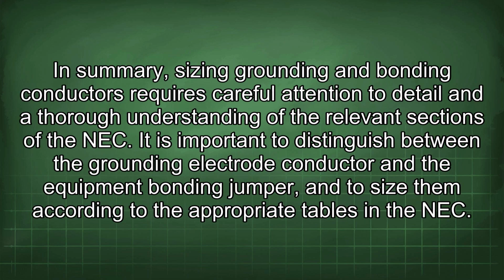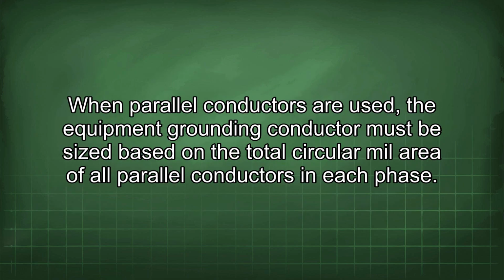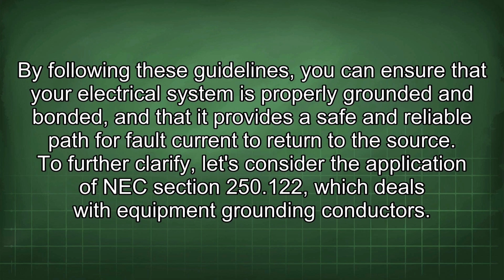In summary, sizing grounding and bonding conductors requires careful attention to detail and a thorough understanding of the relevant sections of the NEC. It is important to distinguish between the grounding electrode conductor and the equipment bonding jumper and to size them according to the appropriate tables in the NEC. When parallel conductors are used, the equipment grounding conductor must be sized based on the total circular mil area of all parallel conductors in each phase. By following these guidelines, you can ensure that your electrical system is properly grounded and bonded, and that it provides a safe and reliable path for fault current to return to the source.